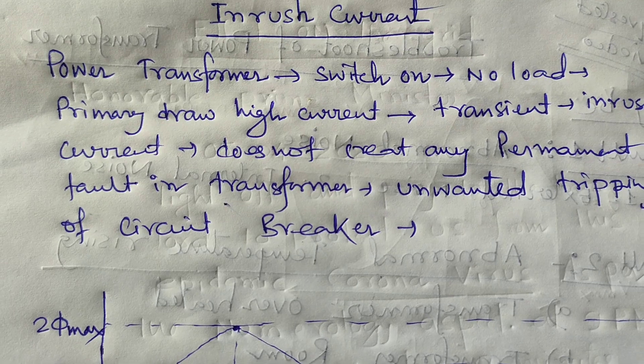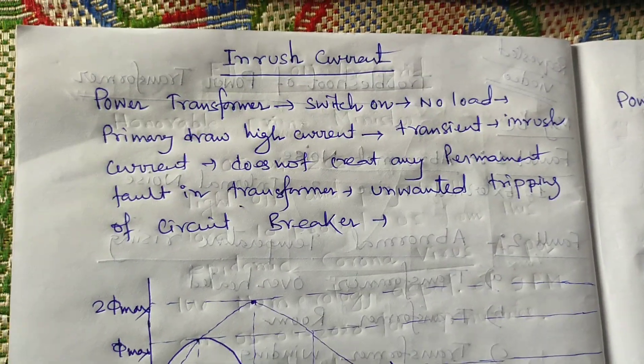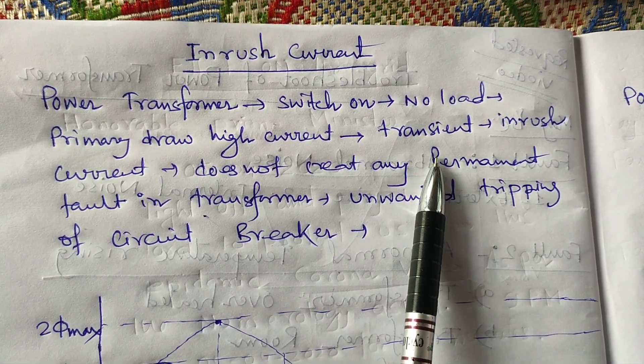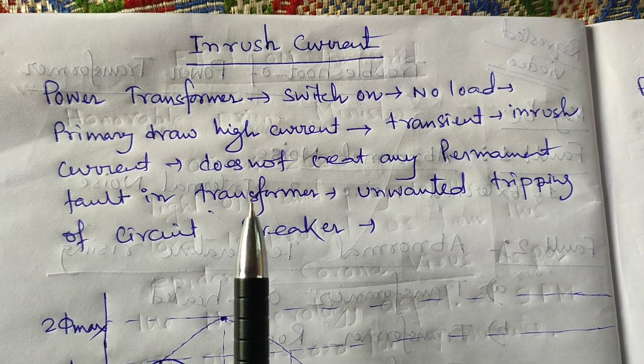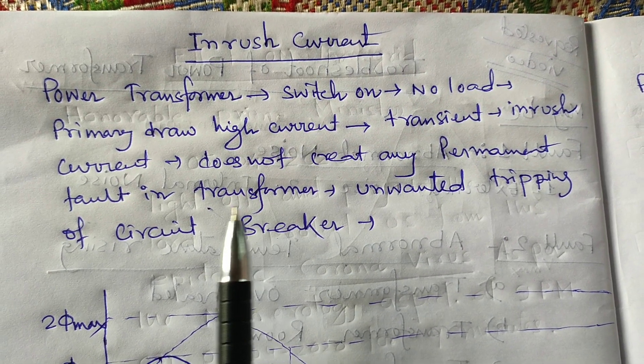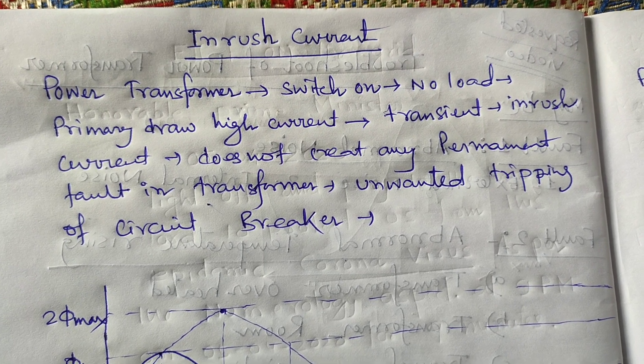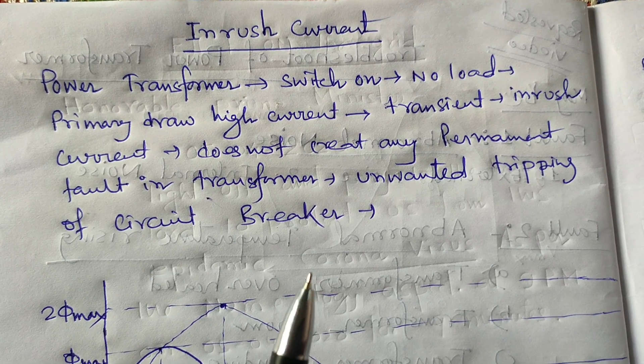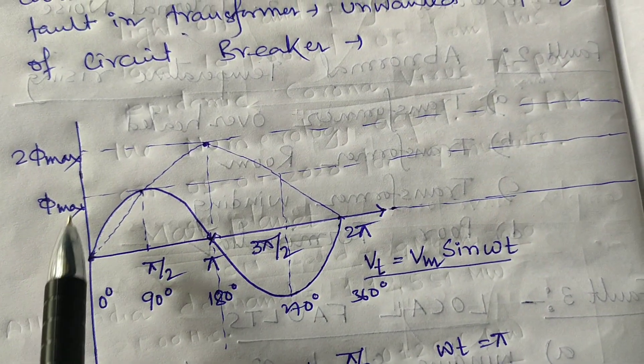When we switch on a power transformer at no-load condition, the high transient current that flows is the inrush current. This inrush current does not create any permanent fault in the transformer, but it may cause unwanted tripping of the circuit breaker. If the circuit breaker trips due to this large current, the transformer may be switched off accordingly.